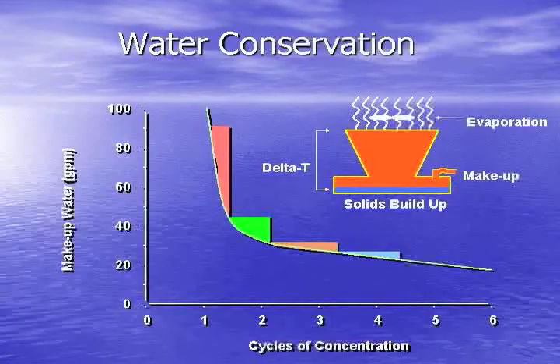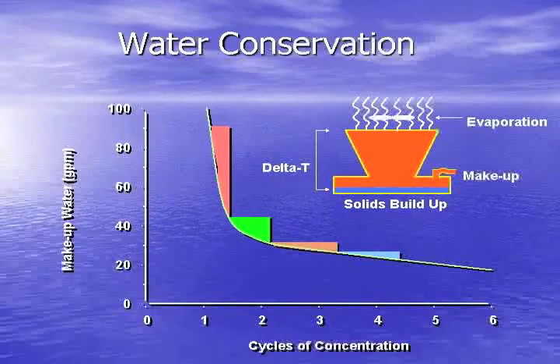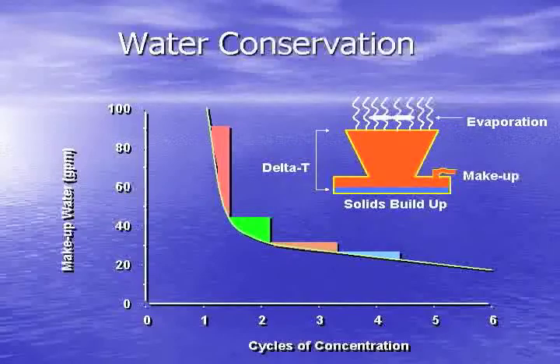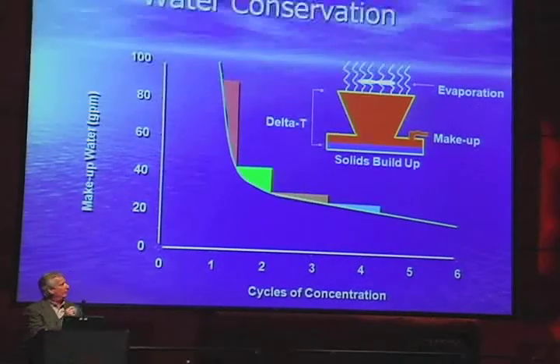And one of the topics I'm going to spend a couple slides on is what we call concentration ratio or cycles of concentration. The more you can concentrate that water, because steam is leaving the tower at the top, so all the minerals stay behind. The more you can cycle that up, the less water you're going to use. And it's pretty drastic. Think about water in, water out, which is probably the worst. If you go down to 2 cycles, you drop 50% water usage.